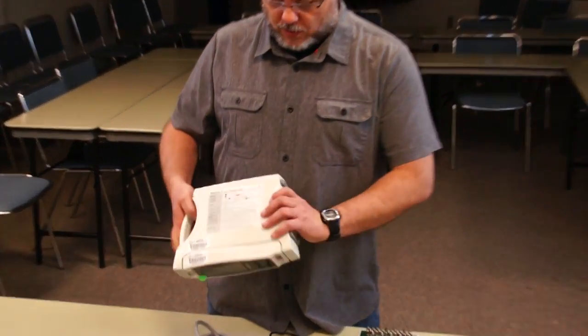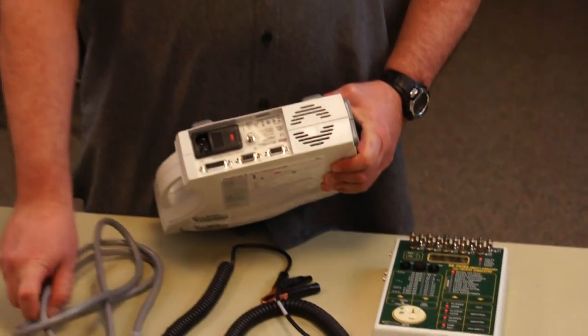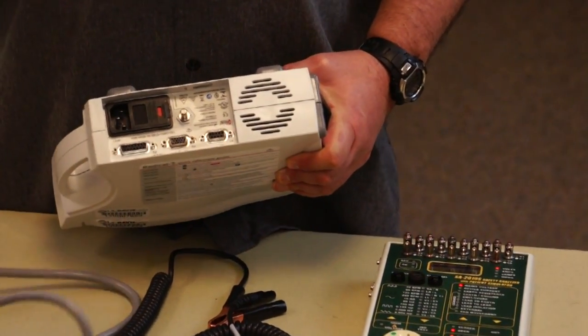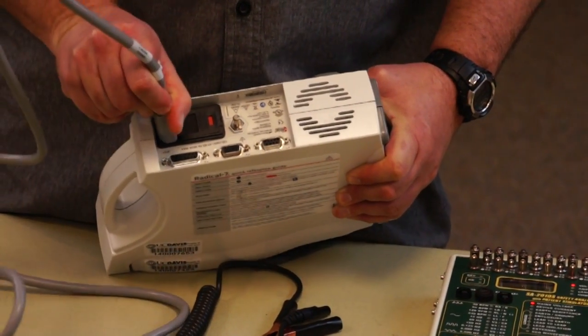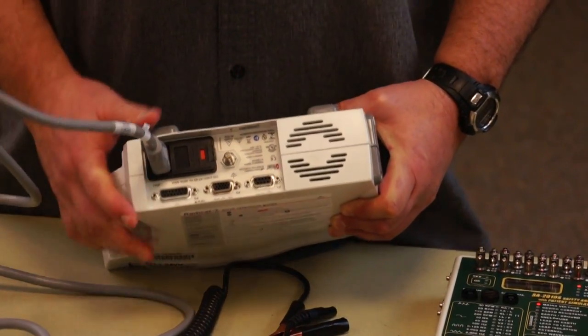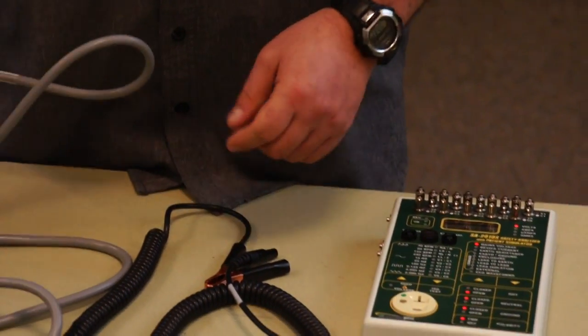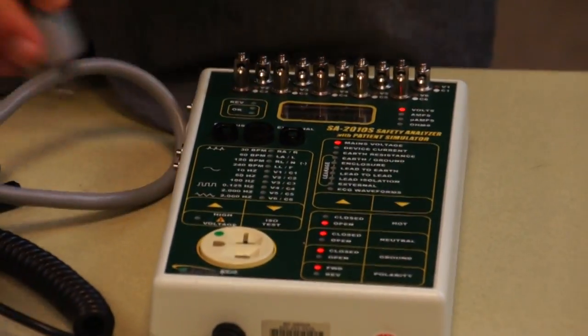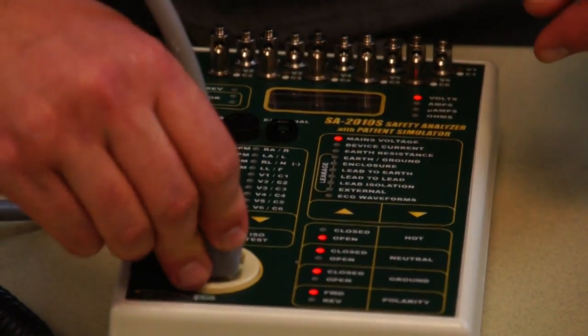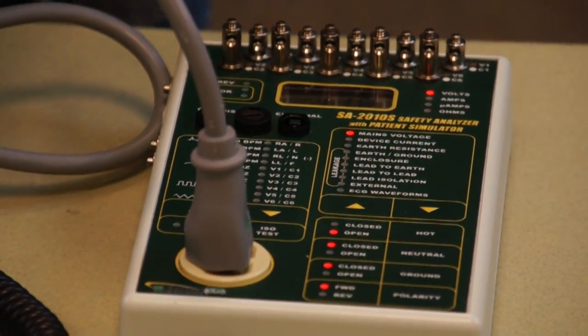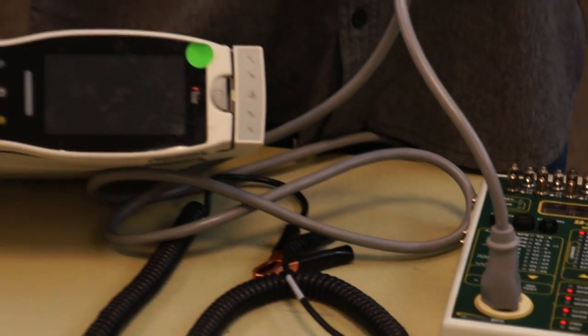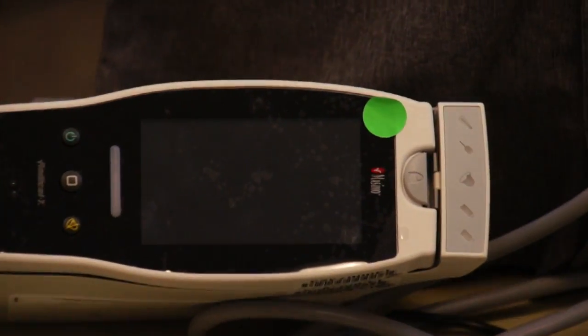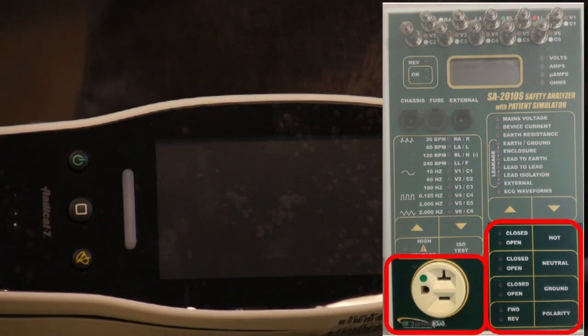Next, we are going to connect our device under test to the safety analyzer. We will plug one end of the power cord to the device under test and plug the other end into the test receptacle of the safety analyzer. I would like to remind you that the test receptacle is not just a pass-through. It is controlled by the safety analyzer.